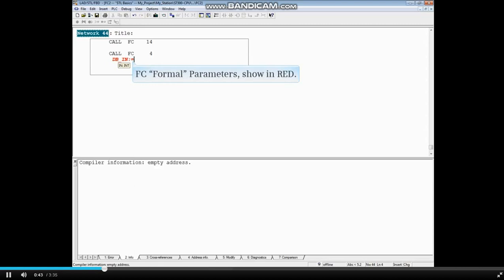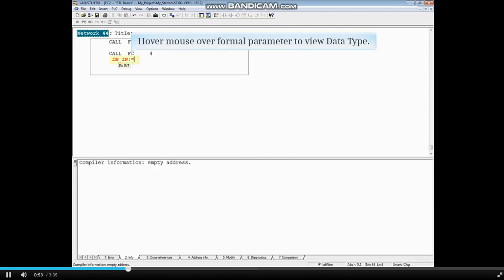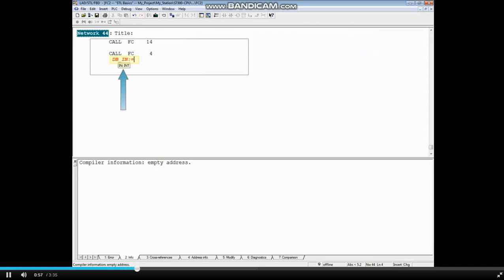Formal parameters for FC calls show in red, which means an actual parameter must be passed before the block can be saved or downloaded. Hover your mouse over the formal parameter to see its data type. This formal parameter is an input with data type integer.